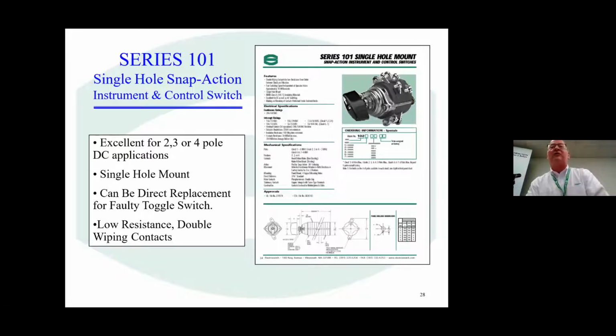So let's say I had a 4-pole switch. For every 90 degrees of operation, I wind up a spring, and at the end of the winding, it snaps into place, which gives me a very high tolerance for DC circuits. It eliminates arcing and faulty replacements of switches, like toggle switches, that can be slowly teased into position and burn up quickly. We use our low resistance double wiping contacts in this switch, and so it's a very highly reliable switch, and it comes in very high current ratings, into the hundreds of amps. So these switches can be very large in stature and in control scheme.